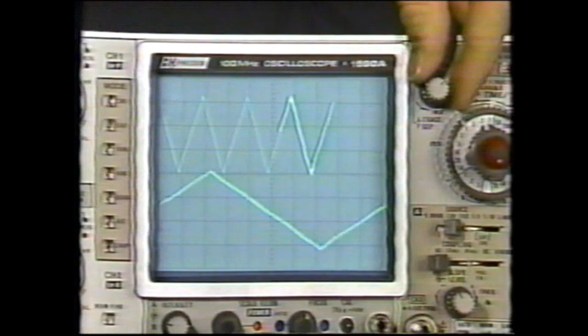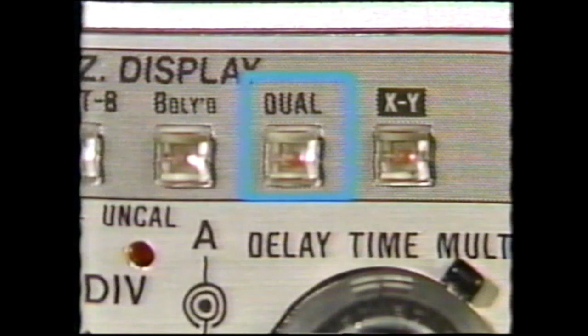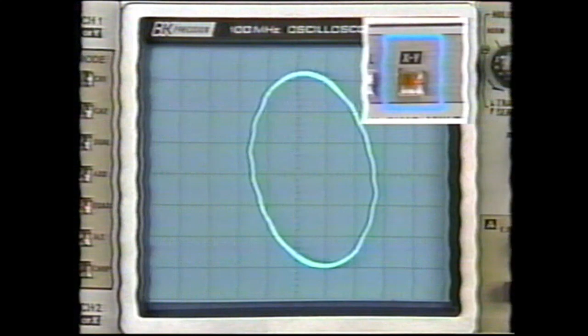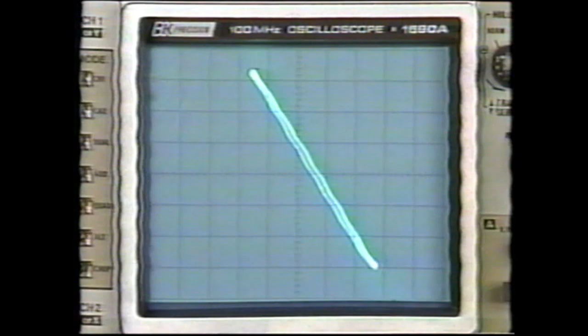In addition, there are 2 other horizontal display modes. In the dual mode, the A and B sweeps operate independently. The A sweep is triggered by the A source, and the B sweep is triggered by the B source. In the XY mode, channel 1 becomes the input signal for the Y-axis, and channel 2 becomes the input signal for the X-axis. In this mode, the X-axis can have characteristics other than time. This is used for viewing semiconductor curve traces, Lissajous waveforms, and for direct comparison of 2 voltages.